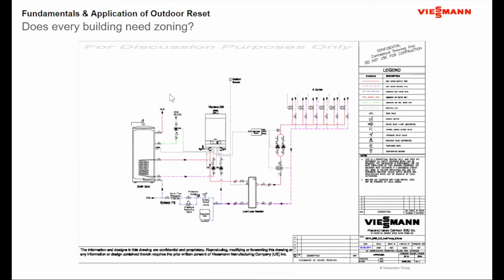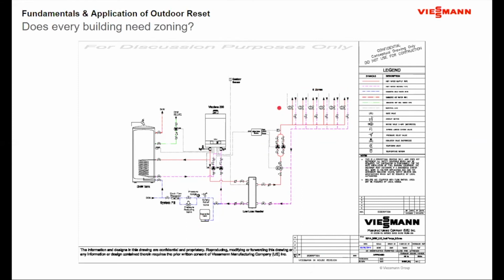So from a piping and control standpoint, I may have a boiler with some methodology of doing outdoor reset control, as seen by the outdoor temperature here, and this sensor strapped on the pipe here, providing the best water temperature needed here. But then because of all variations, let's add an extra level of zoning, so that if there is any variation, say, between these 6 zones, the zoning will allow us to tailor that part of the building for the exact needs of that section of the building. So, with outdoor reset, if a lot of times a question comes up about zoning, my answer always is I'd like to see both in the building because of all those factors we talked about a couple of slides ago.